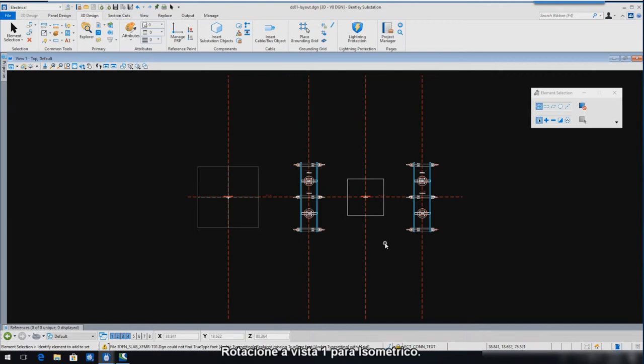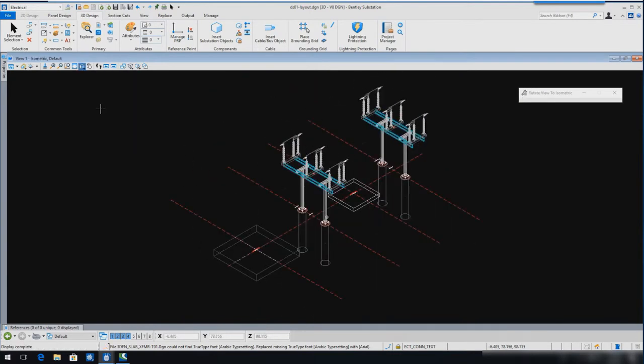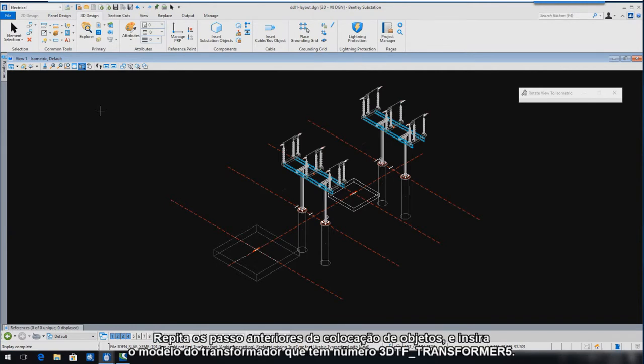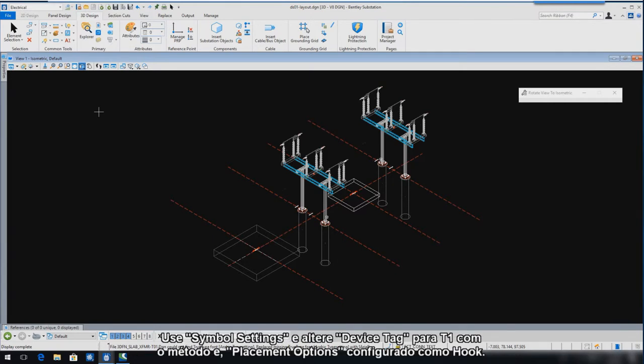Rotate View 1 to the Isometric View. Repeat the previous steps for inserting objects and insert the symbol for Part Number 3DTF Transformer 5. Use Symbol Settings and change the Device Tag to T1 and the Placement Option method to Hook.